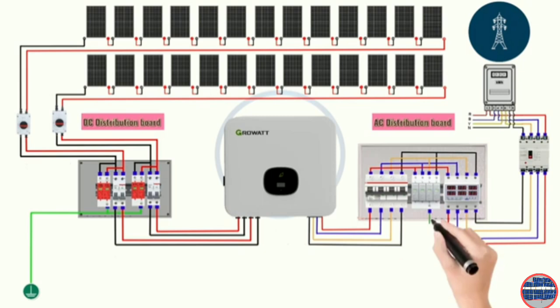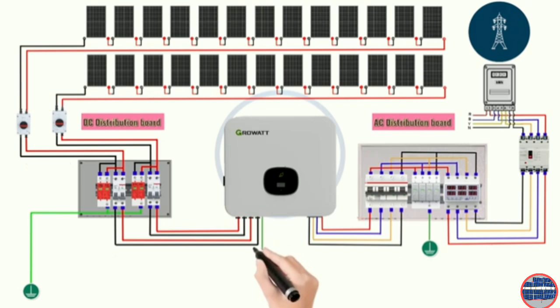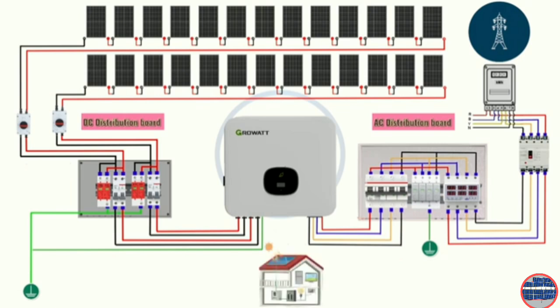The ground wire should be connected to the designated ground terminal on the SPD. Then the SPD is connected parallel to the input of a three-phase MCB, or miniature circuit breaker. The MCB provides overcurrent protection, preventing damage from short circuits or overloads. Make sure the MCB is rated appropriately for your 10 kW system. Finally, the output of the MCB is connected to the AC input terminals of our 10 kW inverter. The inverter converts the DC electricity generated by the solar panels into AC electricity that can be used by your home or fed back into the grid.